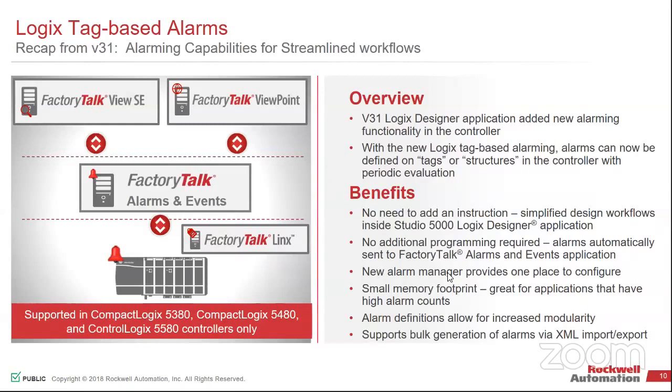And then for everything else, where we can go to the 10,000 level, that would still be on the HMI side. Those are going to be your non-critical, your process-based alarms, a lot of the high temperature ranges where you just want that as informational, and we can mix and match all day long. So what we do here, like I said, is now we have that built into the controller. I'm taking a little bit more memory, but it only exists as version 31 and above. And again, it's a 500 millisecond scan rate on anything that's inside of it.